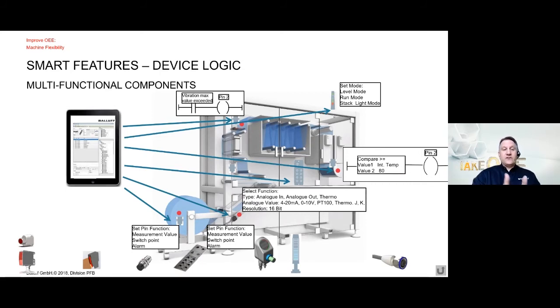You can configure the devices through the engineering tool or the software tool without having to put the logic in the PLC. So you're literally checking a box and setting a threshold when you set up the device. And now you're able to put that functionality at the device on the machine and get this information without having to write that extra code. And you can change this on the fly. So if you decide, hey, I want to change the temperature level or the vibration or whatever it is, you can make that adjustment automatically.